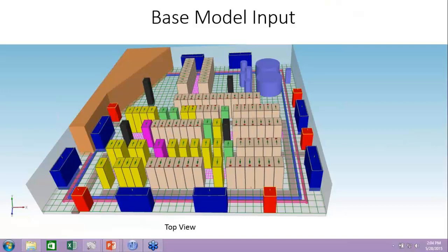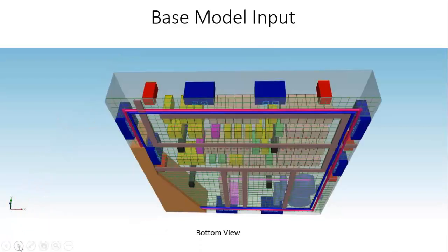Now, also here, we've got an underfloor problem. This is also something I see quite a bit of, a bunch of clutter under the floor. And here we've represented the pipes that run around to these cooling units. They run around the perimeter of the room. And we've intentionally made them quite large to illustrate a few points as we go through this presentation today.